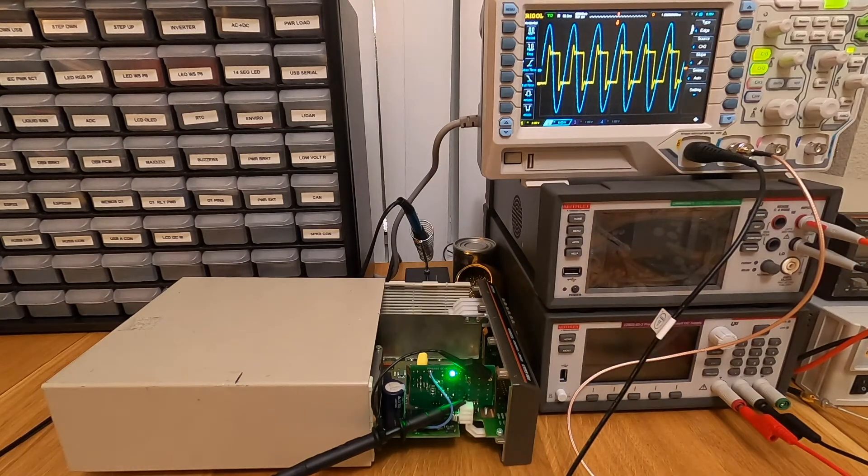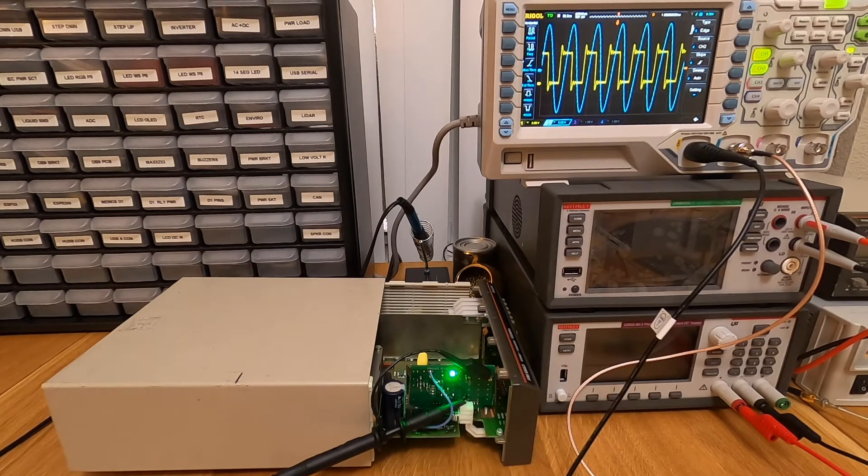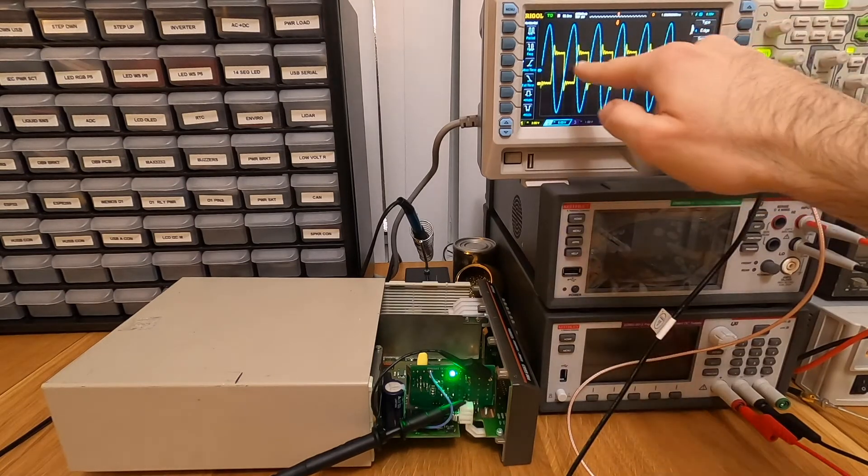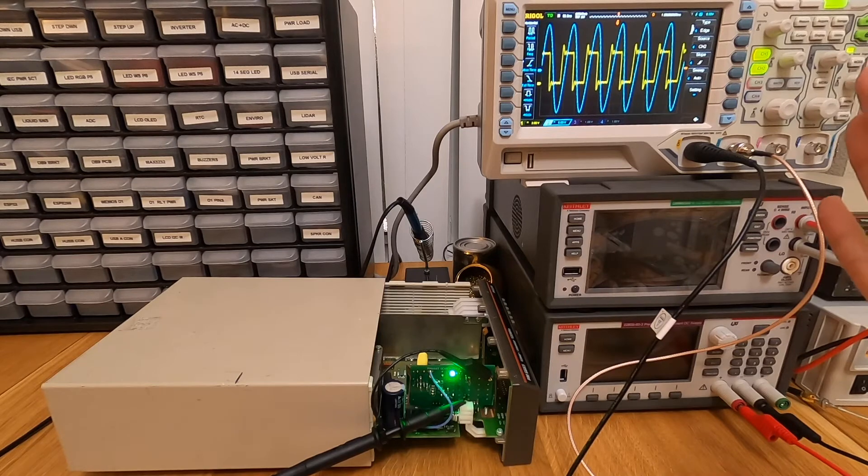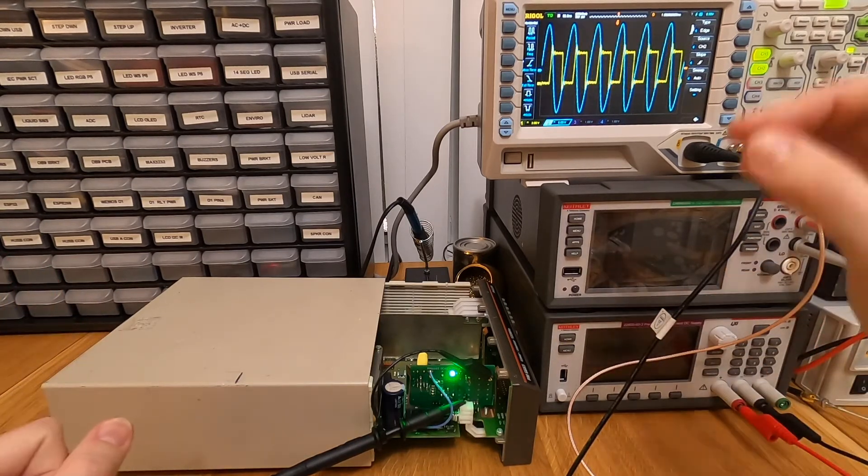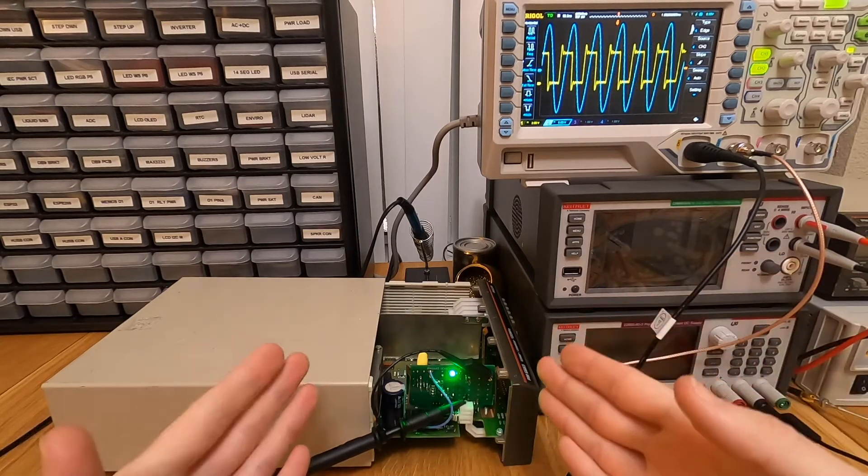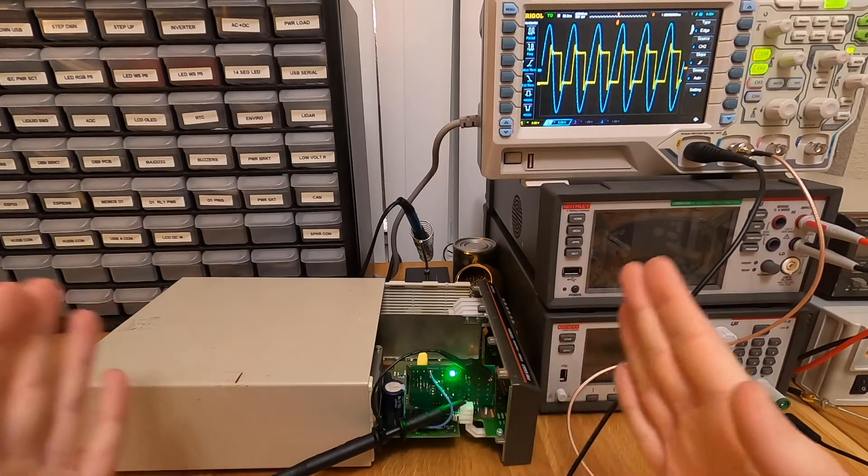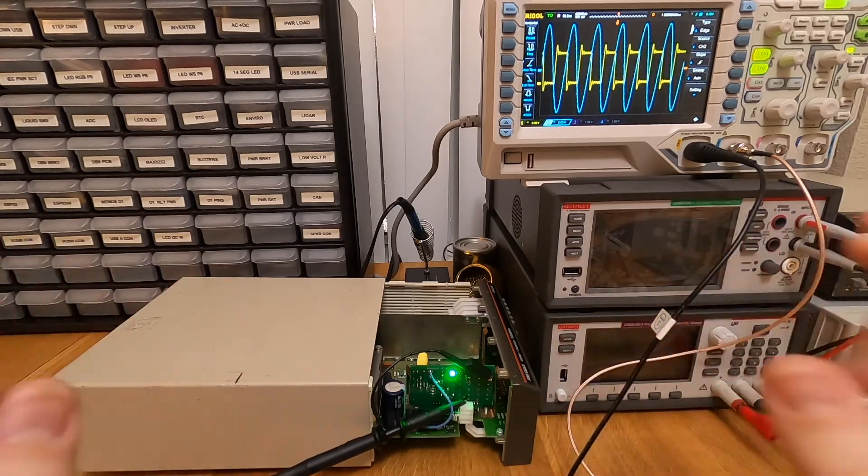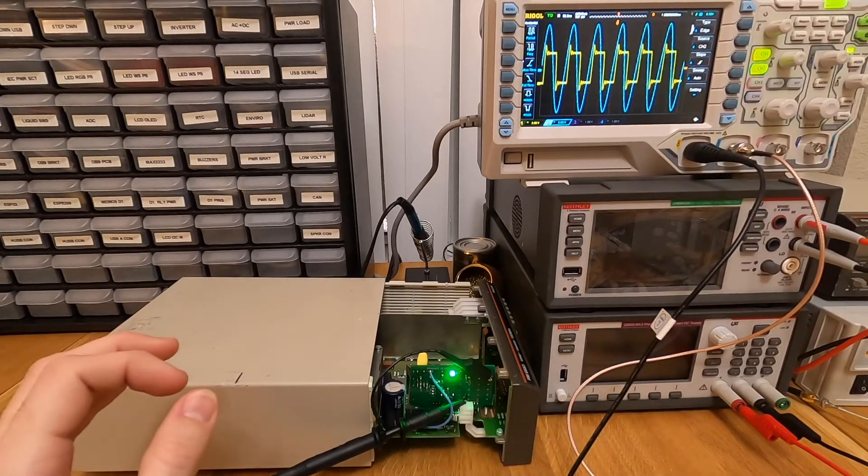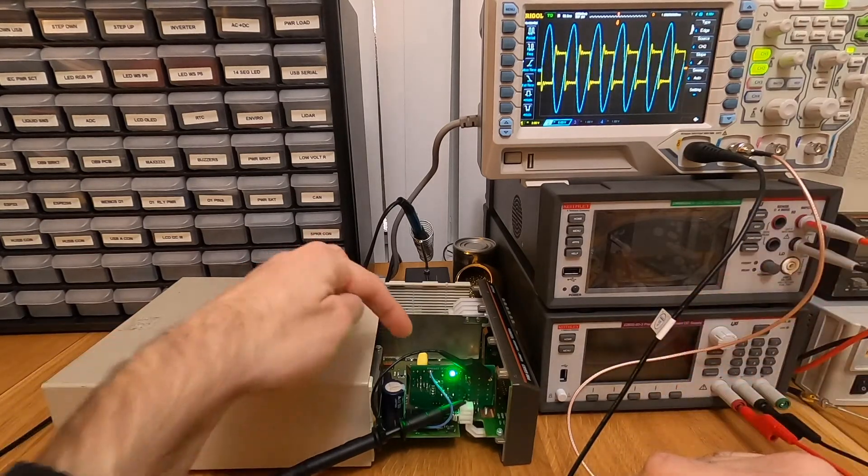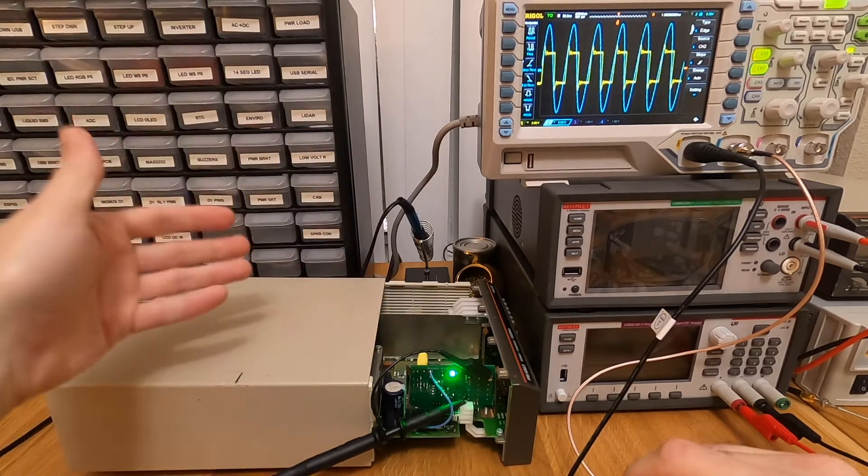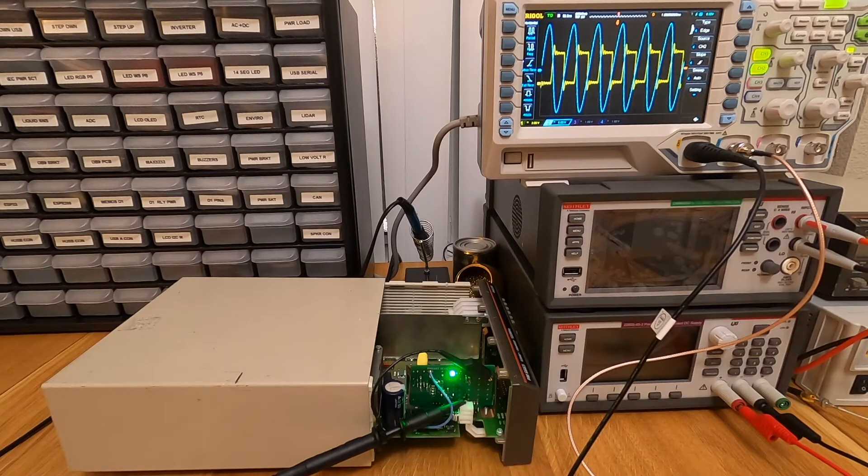So our mission now is to really, really finely tune the frequency output of the OCXO replacement board so that both traces stay aligned as much as possible. And it's not super important to be 100% super precise. The reason for that is we are already at the precision of the reading of the unit. But we want to try to be as close as possible to 10.0000 MHz. But it doesn't have to be 100% perfect. What we want is the precision of the calibration of this frequency source to be higher than the precision of the instrument. If we can achieve that, we are golden.